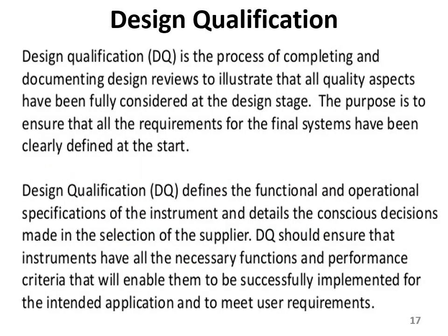Design qualification. Design qualification, DQ, is the process of completing and documenting design reviews to illustrate that all quality aspects have been fully considered at the design stage. While you are designing the process, you have considered all the possible things which you are going to see or face during the process. The purpose is to ensure that all the requirements for the final system have been clearly defined at the start. At the start, you must define each and every thing.